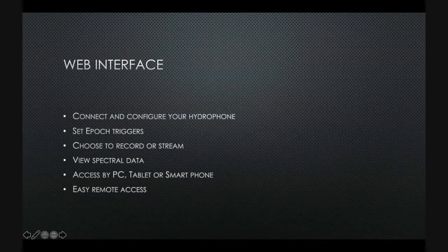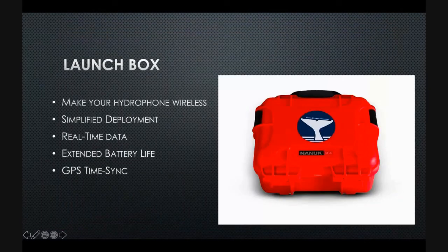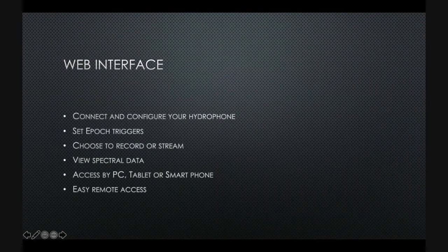The web interface, I'll show you how to use this as well. And what you can use this for is it's a simple way to connect and configure your hydrophone. It allows you to set epoch triggers, you can choose to record or to stream or both. You can view spectral data in real time. And the great thing is that, oh, whoops. Getting a little bit ahead of myself. You can view spectral data and you can access it by PC, tablet, or smartphone. And it allows you easy remote access.